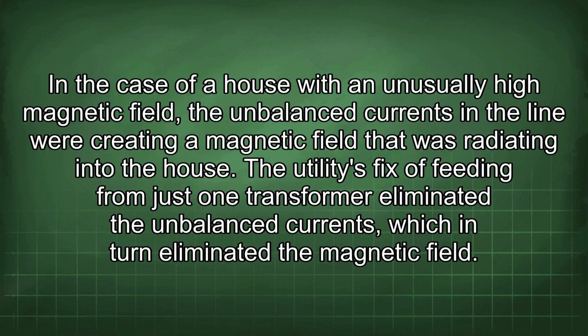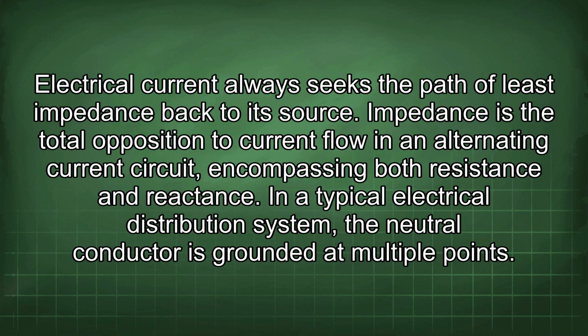In the case of a house with an unusually high magnetic field, the unbalanced currents in the line were creating a magnetic field that was radiating into the house. The utility's fix of feeding from just one transformer eliminated the unbalanced currents, which in turn eliminated the magnetic field. Electrical current always seeks the path of least impedance back to its source. Impedance is the total opposition to current flow in an alternating current circuit, encompassing both resistance and reactance.